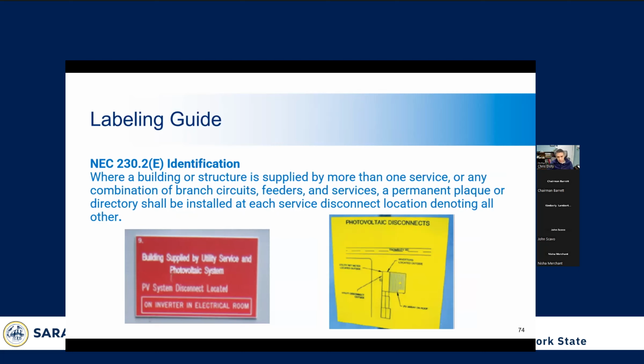For supply side connection, NEC 230.2(E) requires a directory of the location for each service disconnecting means. So you can do that via a map, like on the right here, showing where the disconnects are, or you can do it via a plaque that tells where each disconnect is located. Again, so that whoever's working in it can shut both down and ensure that they're working in a safe condition.